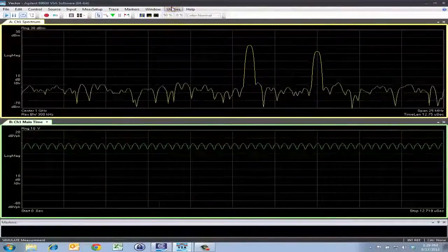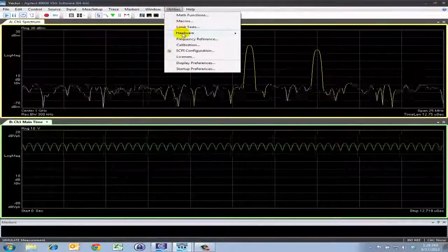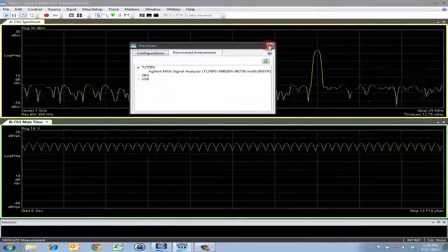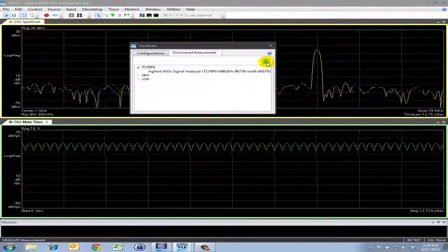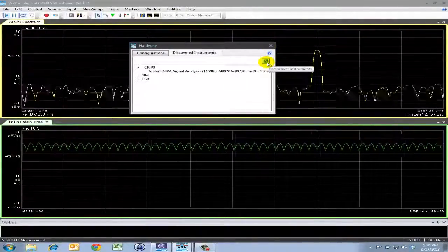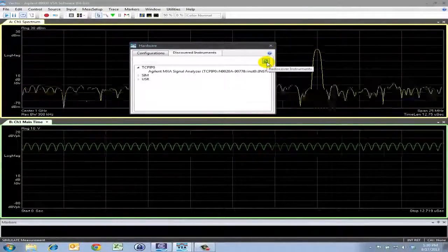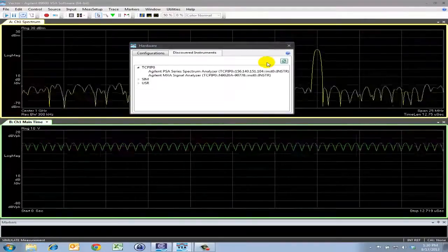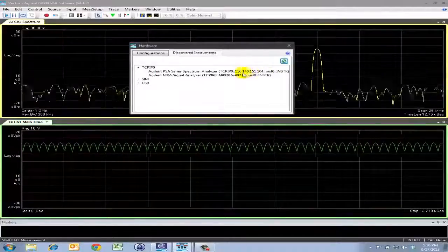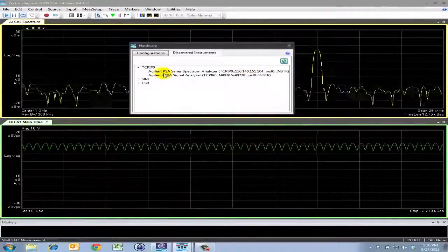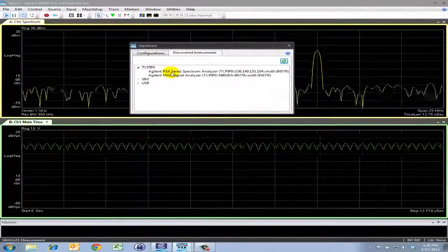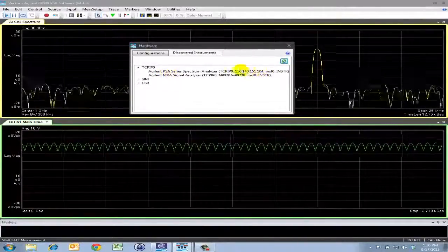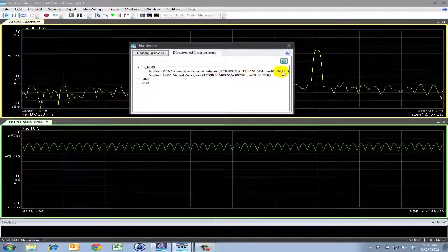I'll go to that same hardware menu under Discovered Instruments and click this green icon here. What this will do is it will go back over the interface bus and check to see any new hardware that it needs to rediscover. So here you'll see that this new PSA analyzer that I've just added has now appeared.